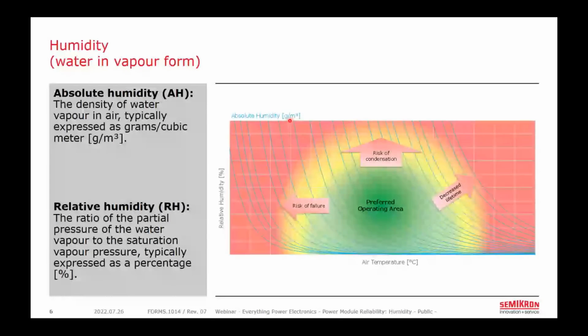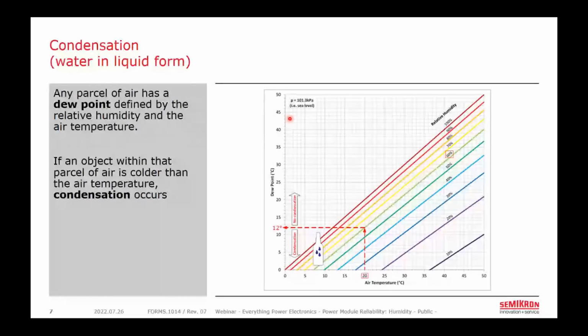So we want to differentiate between that word humidity, which is water in vapor form, and condensation, which is water in liquid form. This is important because in a few slides, we will discuss how you can have failures of power electronics in high humidity environments without obvious condensation. But nevertheless, condensation is a risk anytime you have an object that drops below the dew point for a given environment. The most relatable example is a bottle of cold liquid taken from a refrigerator and put out into a room where you have beads of water, which are condensation, forming on the sides of that bottle.